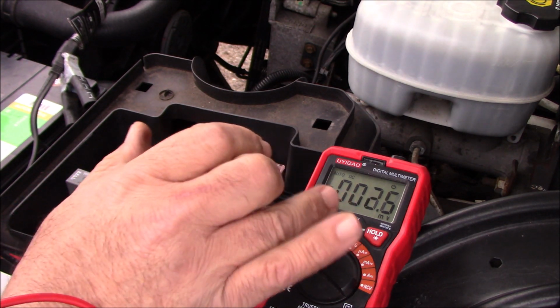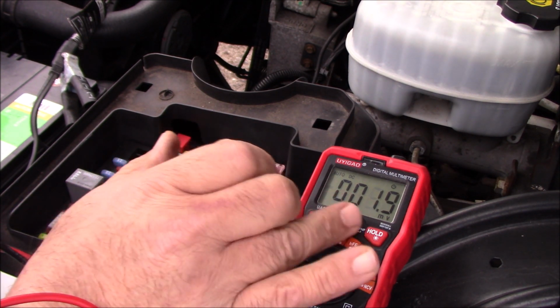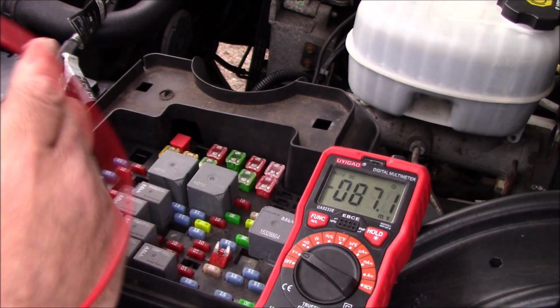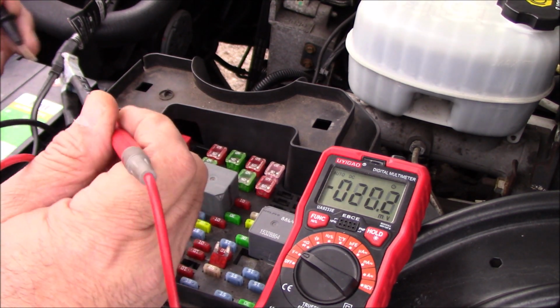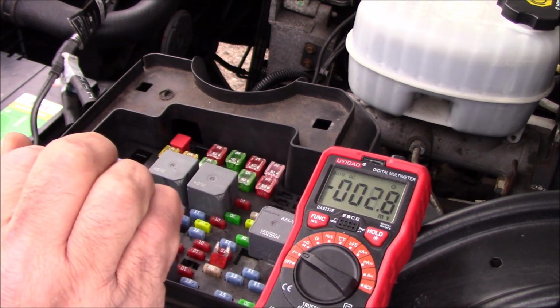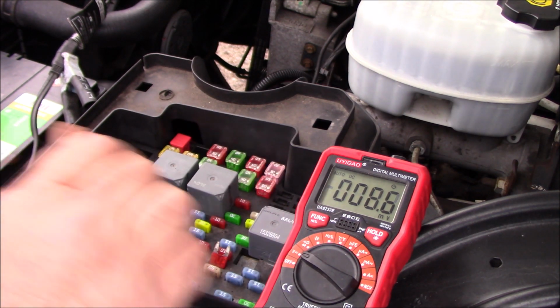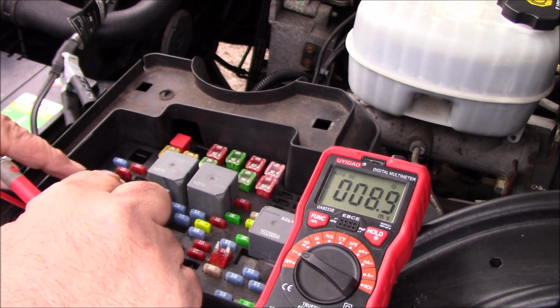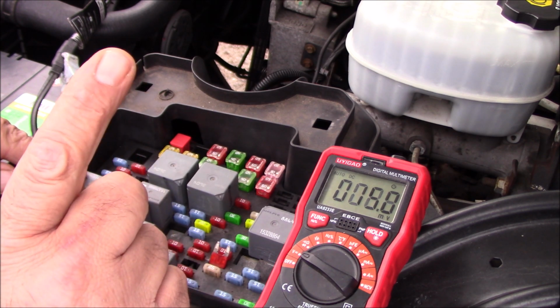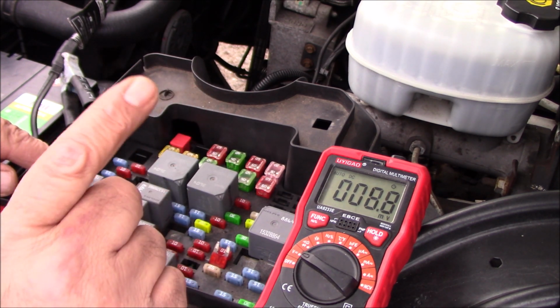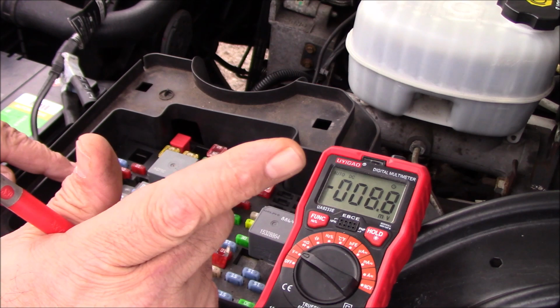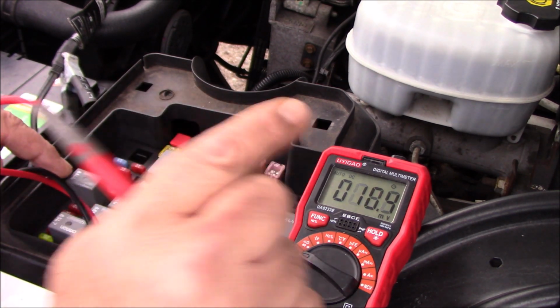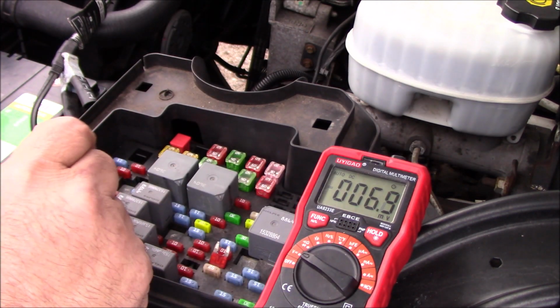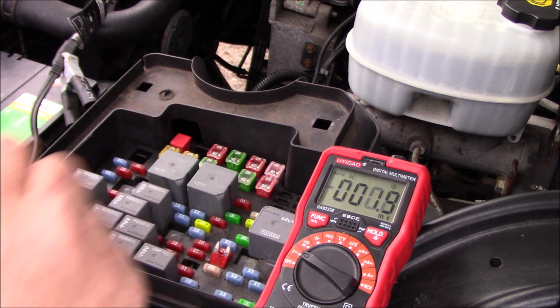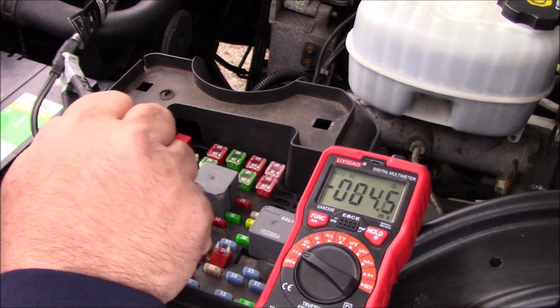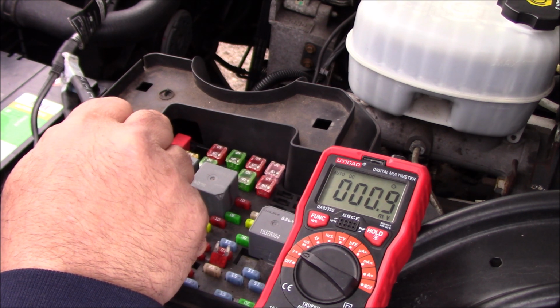If you see millivoltage going through, that's just my meter jumping around because nothing's connected. But if you see, say, 3.5 millivolts going across a fuse, that means there's current flowing through it. What you'd do then is go to a chart — Power Probe makes one that converts the fuse type and the millivolts you see to an amp draw. I'll link the Power Probe chart in the description below to help tell you how much your draw is.